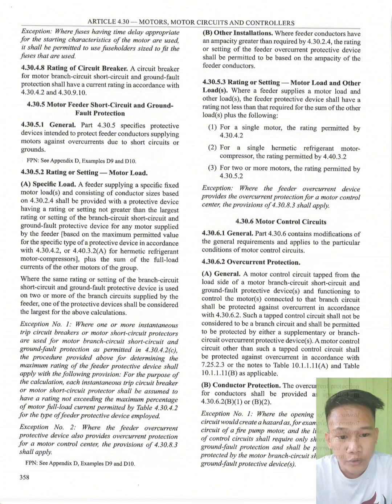Motor branch circuit and ground fault protection under Article 4.30, motor circuits and controllers. So we have here the rating of circuit breaker. A circuit breaker for motor branch circuit, short circuit, and ground fault protection shall have a current rating in accordance with 4.30.4.2. So, what is that? The maximum rating or setting of motor branch circuit, short circuit, and ground fault protective device. If you remember, there was a table. Then 4.30.9.10. So we will tackle this later in our discussion.